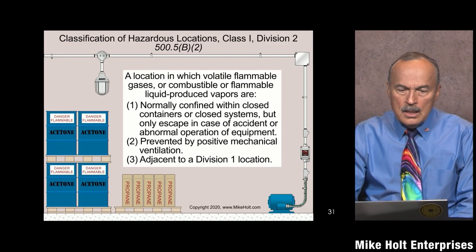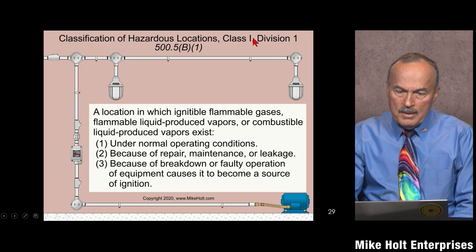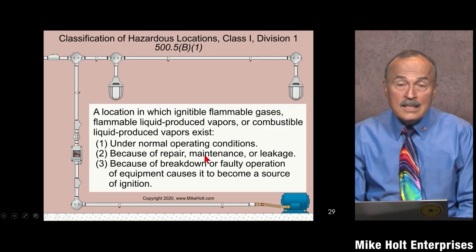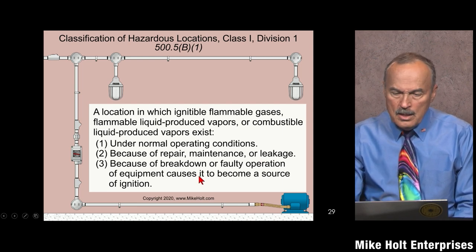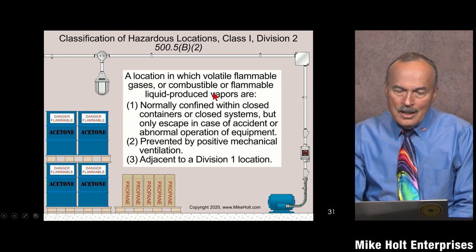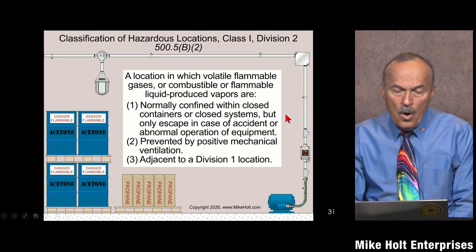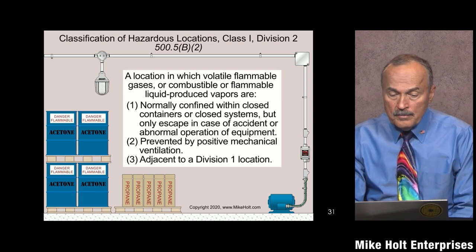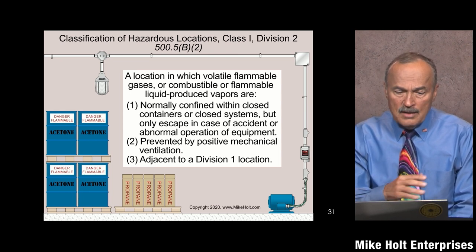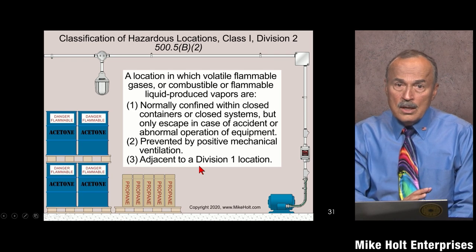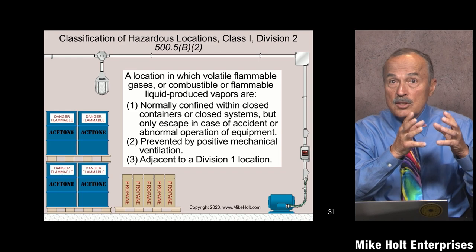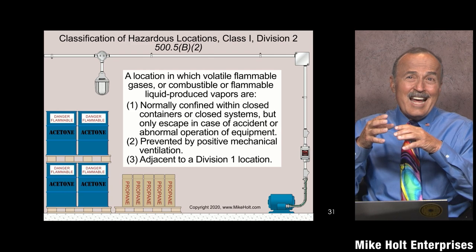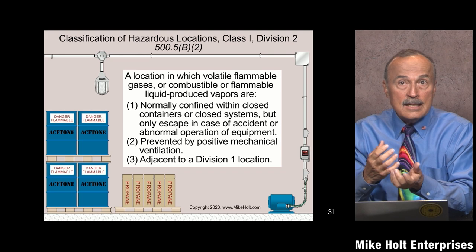Class 1 Division 1 is about gases being present under normal operating conditions — repair, maintenance, leakage, or failure. Class 1 Division 2 is where the gas is normally confined within closed containers or closed systems, but only escapes in case of an accident or abnormal operation, or where ventilation mitigates exposure, or it's adjacent to a Class 1 Division 1 location transitioning to a non-classified area.